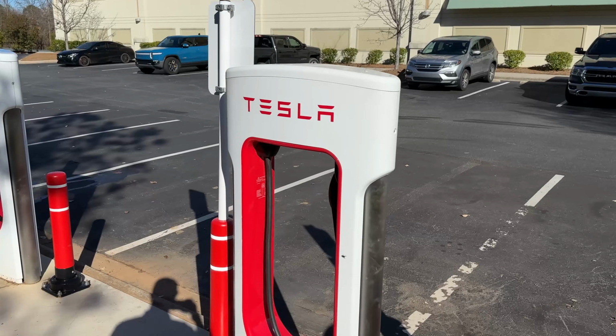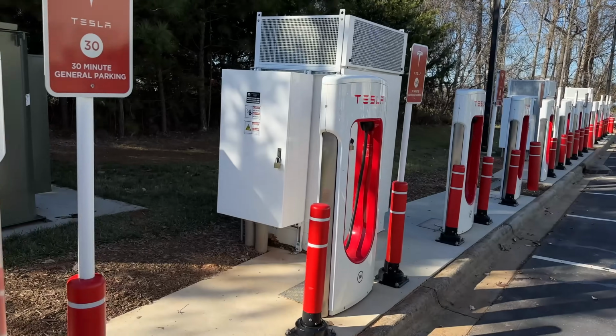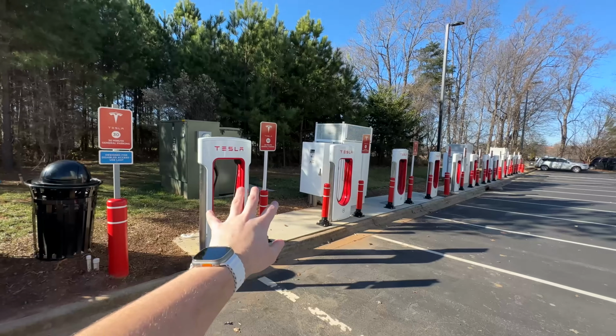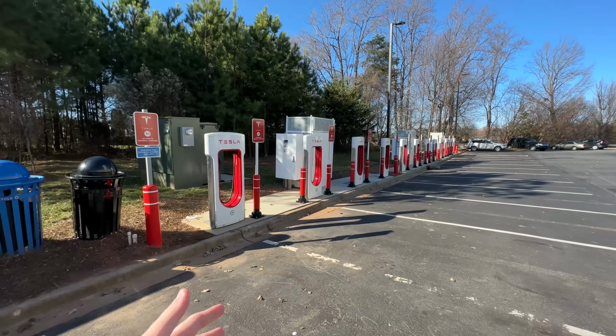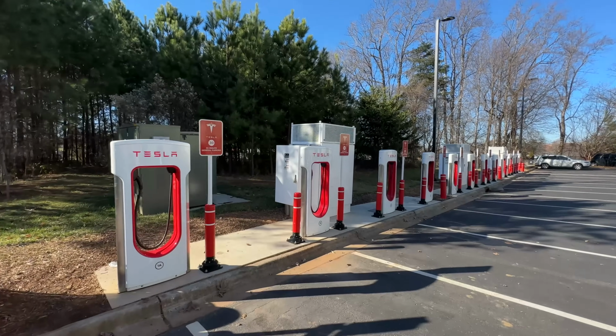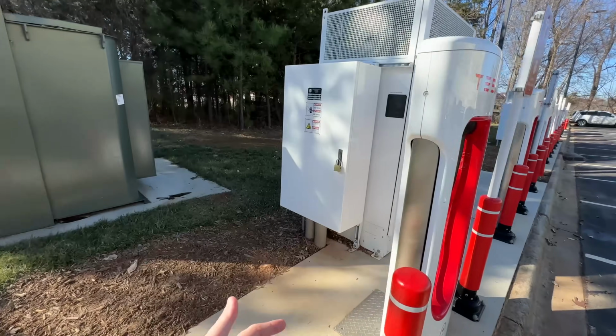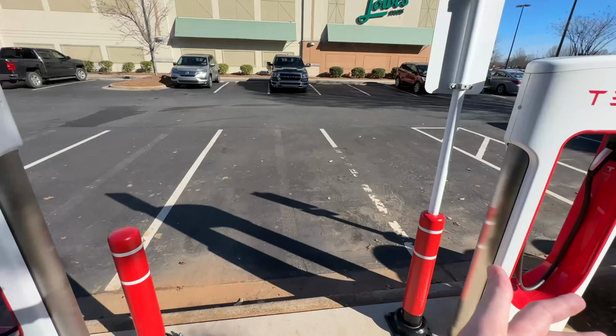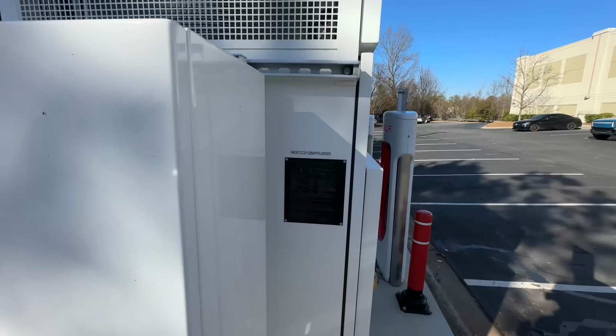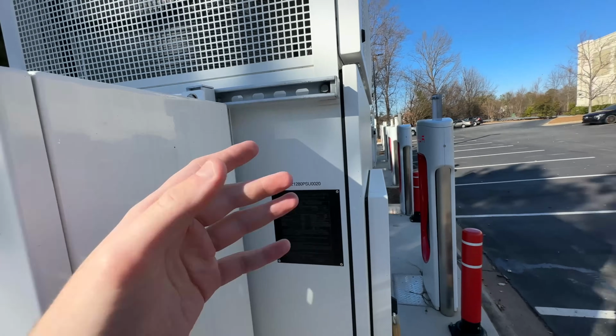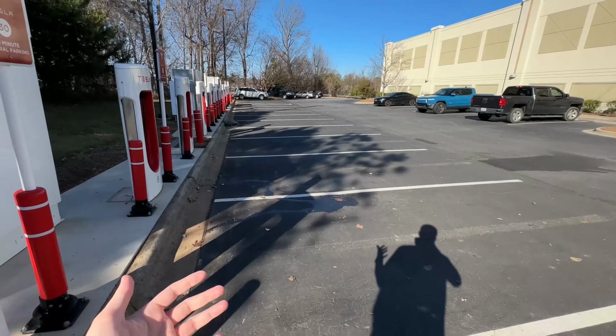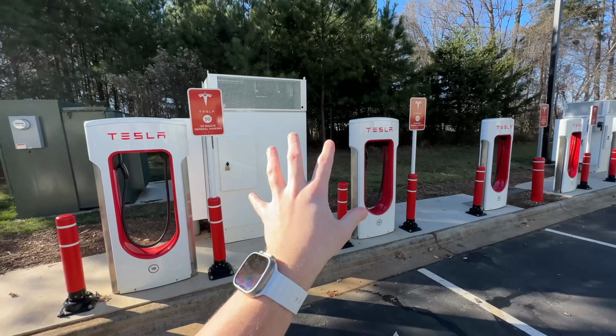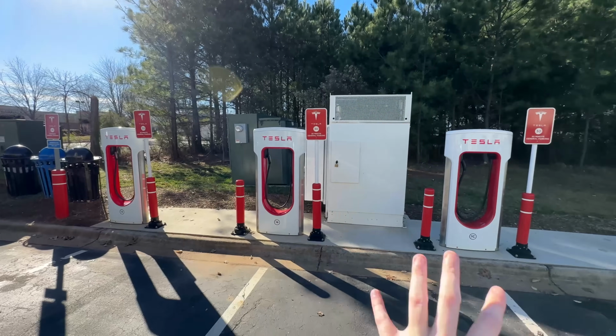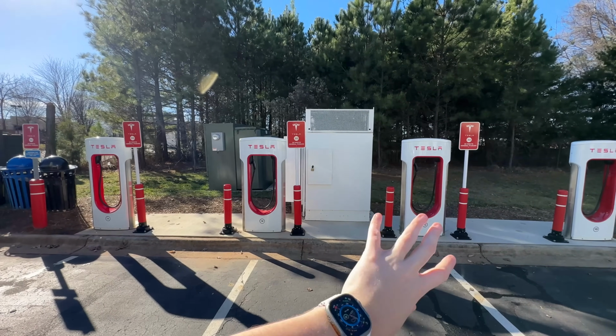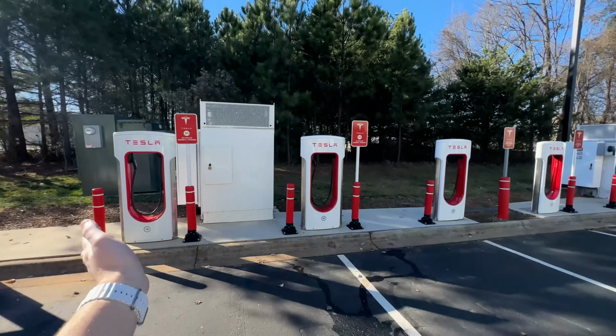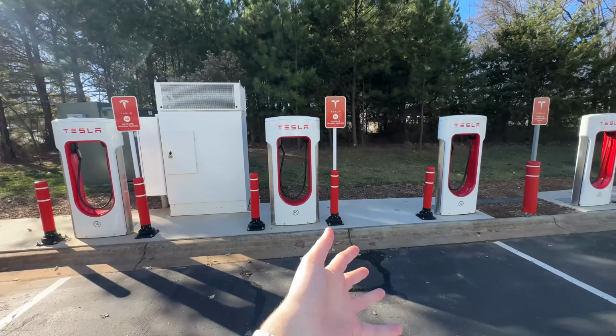We then have a 12 stall version 3 Tesla supercharger. Version 3 means these can actually output up to 250 kilowatts at each stall. However, each cabinet is not 1,000 kilowatts, which would be implied by having four pedestals or posts, as Tesla calls them, per cabinet. With the version 3 supercharger architecture, you actually have four posts per one cabinet. Typically the cabinets are all next to each other, and then you have a row of posts or islands, depending on the site configuration.